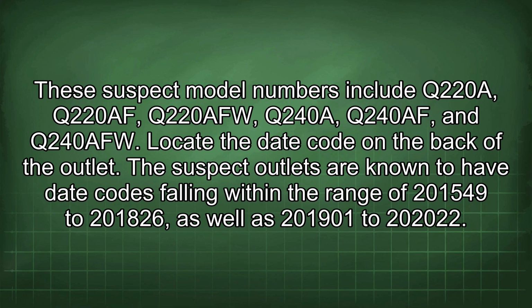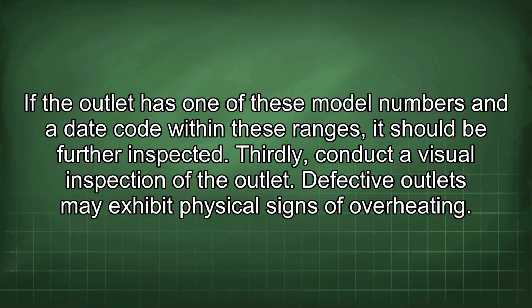Locate the date code on the back of the outlet. The suspect outlets are known to have date codes falling within the range of 201549 to 201826, as well as 201901 to 202022. If the outlet has one of these model numbers and a date code within these ranges, it should be further inspected. Thirdly, conduct a visual inspection of the outlet.